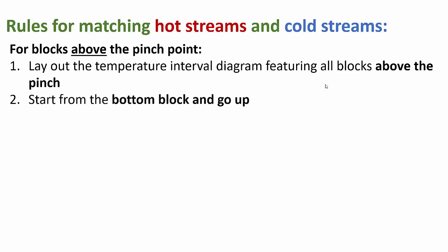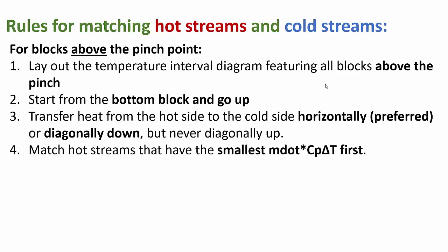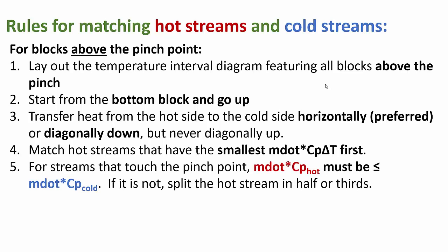We always start from the bottom block and go up. We transfer heat from the hot side to the cold side horizontally or diagonally down, but never diagonally up — we will see why that isn't physically possible. We match hot streams that have the smallest M_dot·Cp·ΔT first — in other words, we match hot streams that have the smallest Q first — and we usually match them with cold streams that have the largest Q or the largest M_dot·Cp. For streams that touch the pinch point, M_dot·Cp hot must be less than or equal to M_dot·Cp cold. If it isn't, then we split the hot stream in half, thirds, or quarters so that M_dot·Cp hot is less than or equal to M_dot·Cp cold.